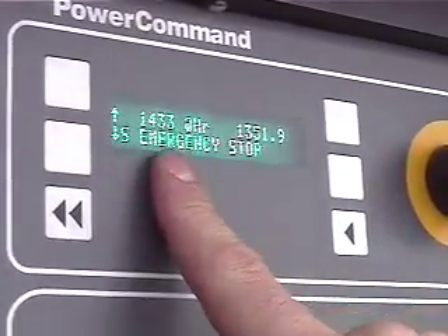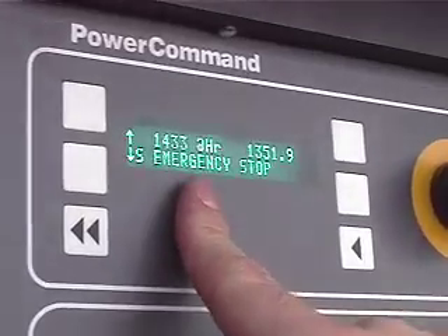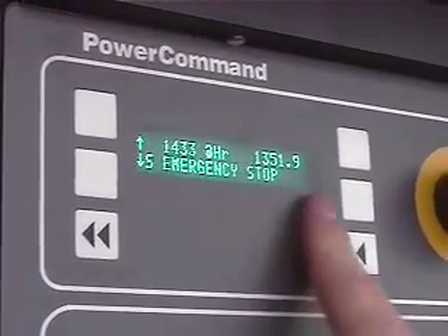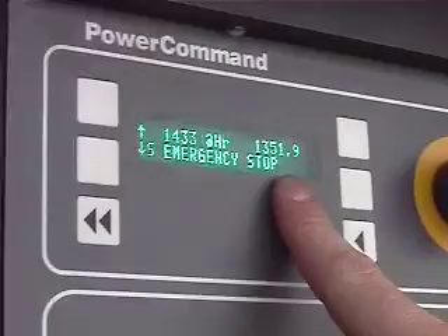Okay, fault code 1433 is a local emergency stop. That fault happened at 1351.9 control hours. It's not engine hours, it's control hours. That's basically how much time has gone by since the batteries have been installed. It's going to count all the way up to, I think, 33,000 hours, and then it'll start over, counting back up. Down at the bottom it tells you what it is. An S means it's a shutdown. Okay, the fault, and then the fault name.